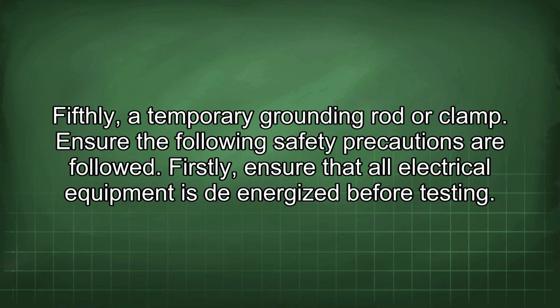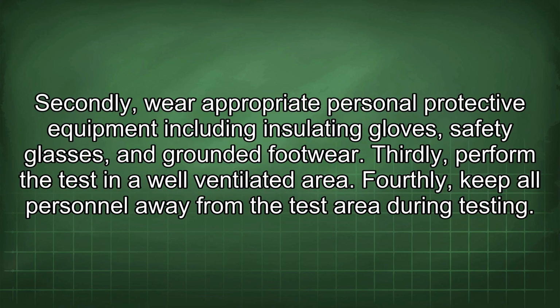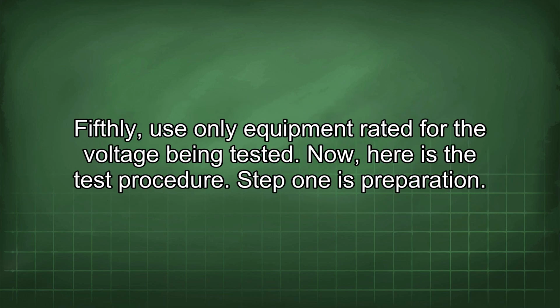Ensure the following safety precautions are followed. Firstly, ensure that all electrical equipment is de-energized before testing. Secondly, wear appropriate personal protective equipment including insulating gloves, safety glasses, and grounded footwear. Thirdly, perform the test in a well-ventilated area. Fourthly, keep all personnel away from the test area during testing. Fifthly, use only equipment rated for the voltage being tested.